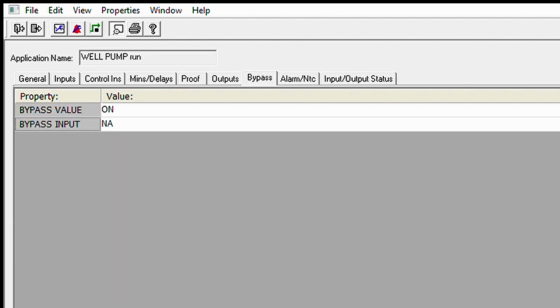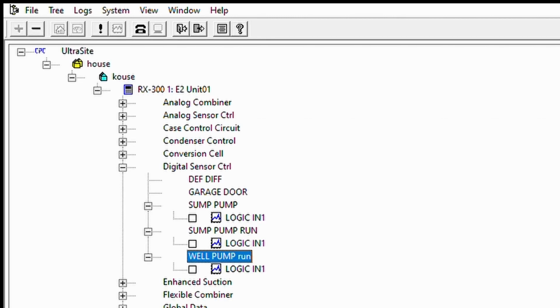The one thing I will tell you is with digital stuff, whether it's an output or a digital sensor control, you're better off making a second log group and not putting it at the base log, so it isn't logging every 2 or 3 minutes. Because in that 2 or 3 minutes, you could be cycling that input on and off multiple times. So you're better off putting a second log group and putting it to like 30 seconds, so that your logs go a lot quicker, because you may not catch it in that 3 minutes going on and off.